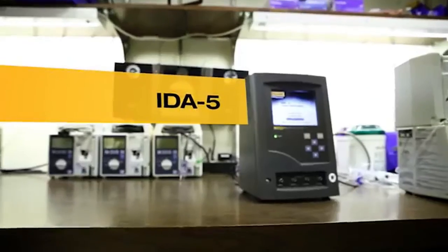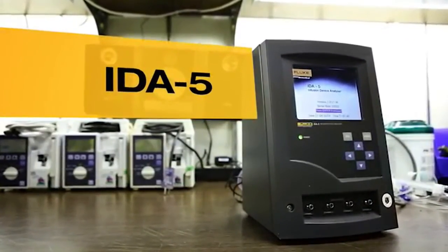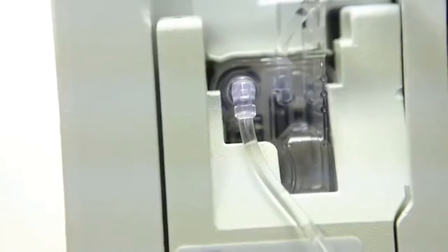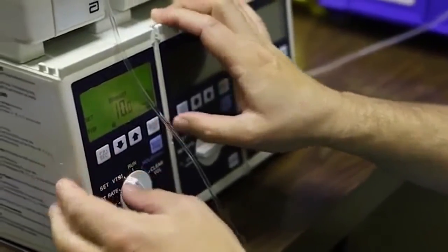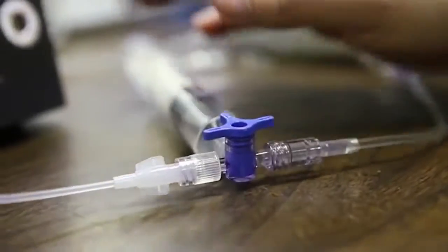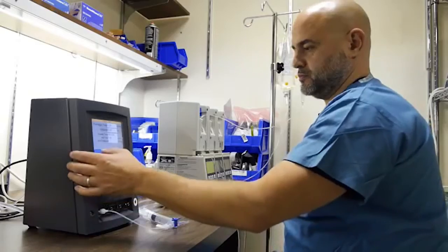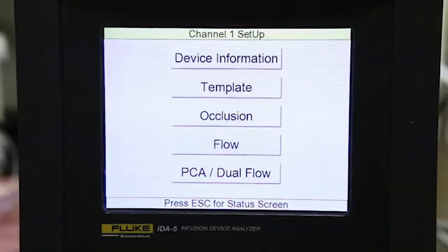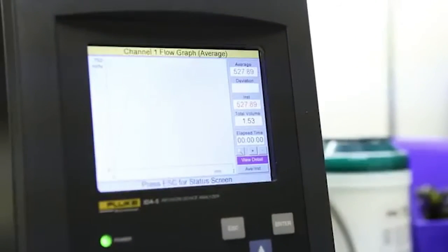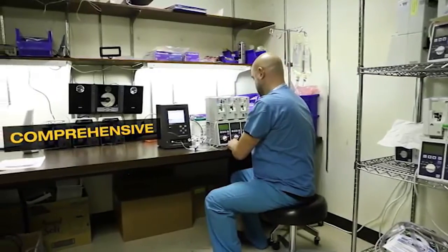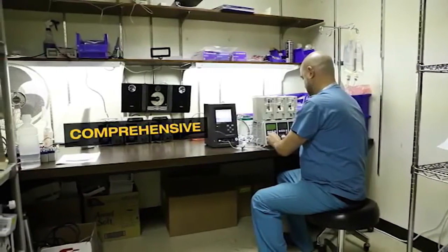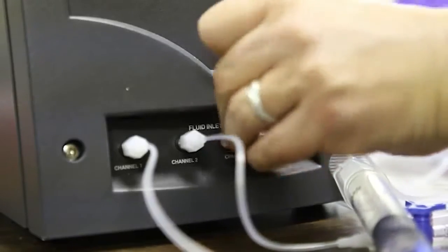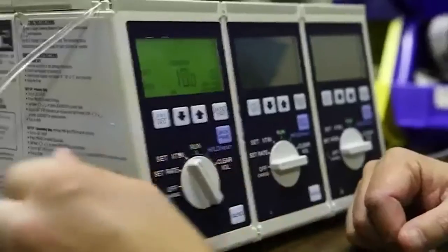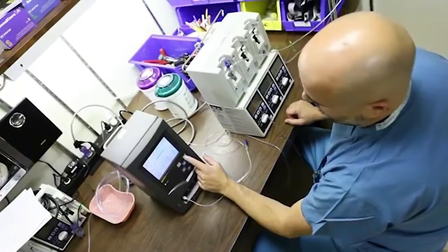Hi, my name is Sławian Angelov and I'm a biomedical equipment technician. The IDA5 is really accurate and fast. We use Hospira infusion pumps. Before we used the IDA5, we didn't have any idea what the percentage of air was. And now with the analyzer, it's way easier to find the exact numbers. You can precisely see what the volume is, what the flow is, and what the pressure is. And then you know if the pump works right or not. You can hook up 4 pumps at the same time. The IDA5, it just does the job. I think people will be really surprised to find how much easier their job can be once they use it.